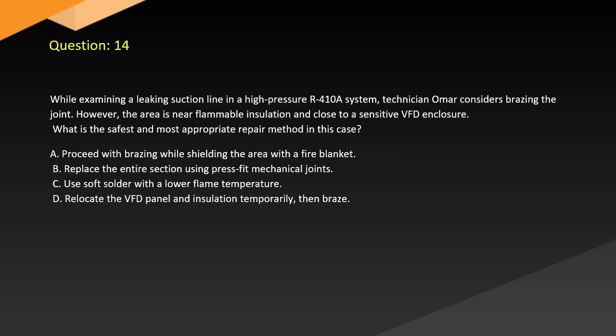Question 14. While examining a leaking suction line in a high-pressure R-410A system, technician Omar considers brazing the joint. However, the area is near flammable insulation and close to a sensitive VFD enclosure. What is the safest and most appropriate repair method in this case? A. Proceed with brazing while shielding the area with a fire blanket. B. Replace the entire section using press-fit mechanical joints. C. Use soft solder with a low flame temperature. D. Relocate the VFD panel and insulation temporarily, then braze.